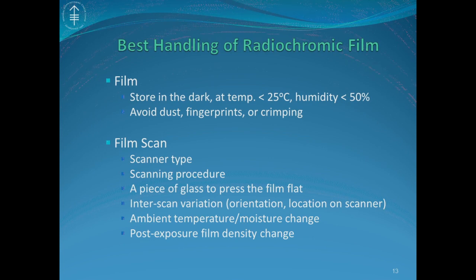Now let's go over how to handle radiochromic film. In order to optimize the useful life of the film, it is suggested to store the film in the dark at a temperature under 25 degrees Celsius, and average humidity less than 50%. Try to avoid dust, fingerprints, or crimping.